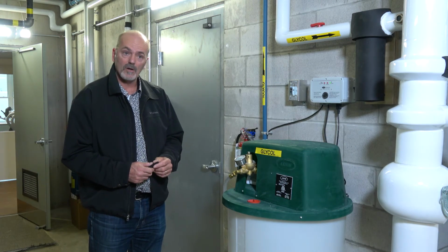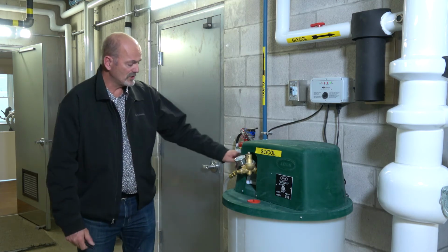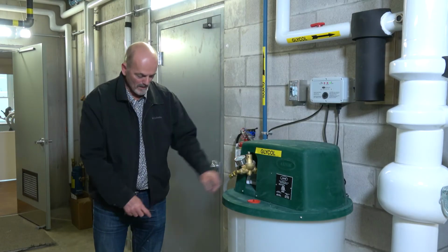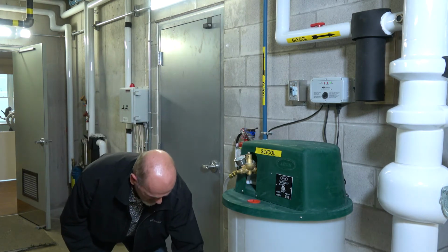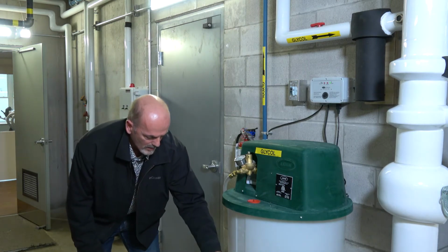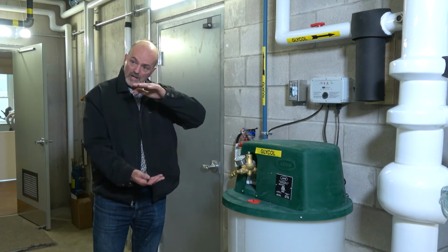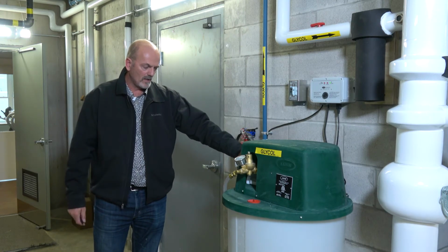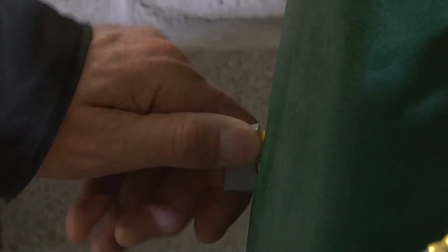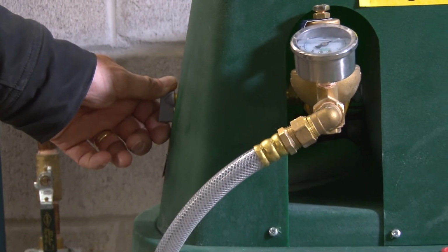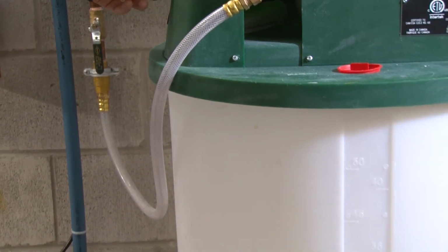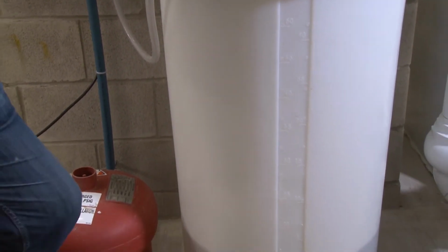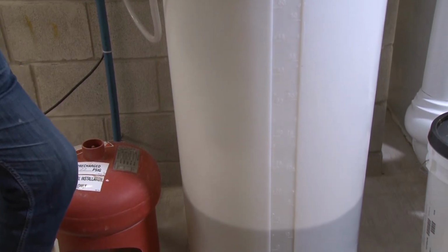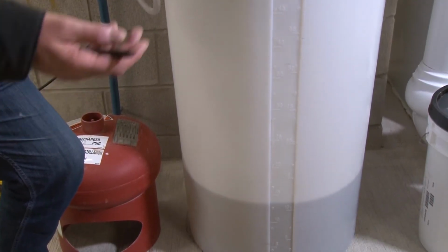If you're not doing premixed glycol and you're doing water and glycol, there is a function here where you can put your water in, and there's gradients on the tank, okay? So you can put equal portions of 100% water and 100% glycol, top it up to whatever level, and then you should really mix it, okay? Because they're two separate fluids, they won't necessarily mix. So there is a mix feature just strictly by turning this valve 90 degrees. It allows it to pump back into itself and mix. You can see the agitation on the tank in the water, and the glycol is mixing. Then you close it back up, and hopefully it will shut off and pressurize. That's what the pump basically runs like. You can hear it.